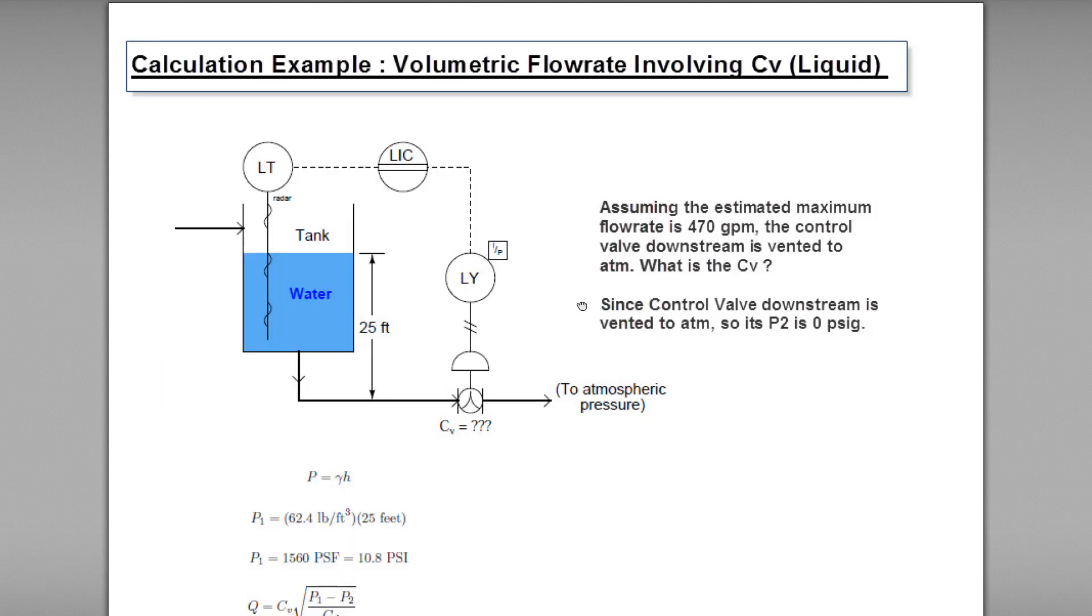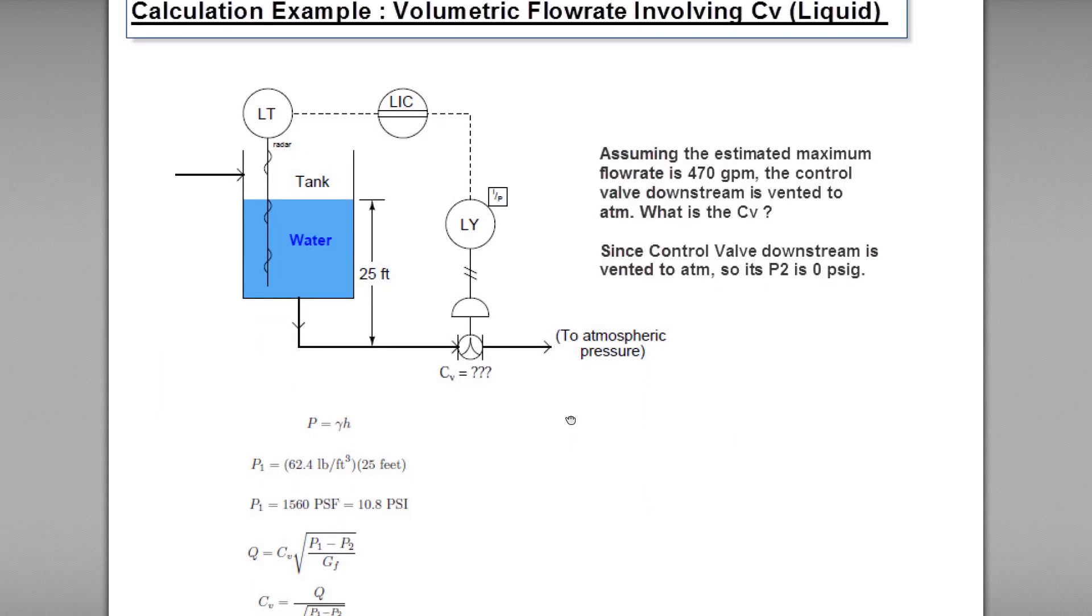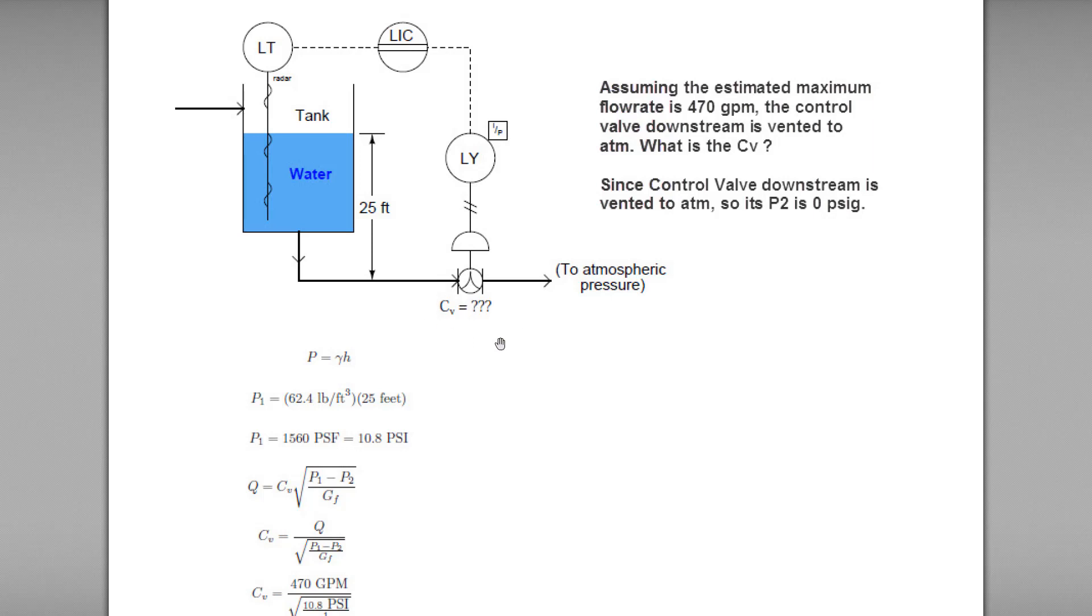So now we can come to the calculation part to calculate the CV or flow coefficient. Assuming that the estimated maximum flow rate of the liquid is 470 gallons per minute. The control valve downstream is vented to ATM, that means atmosphere. What is the CV? As we know, since the control valve downstream is vented to ATM or atmosphere, the downstream pressure P2 is 0 psi G. G mean gauge.